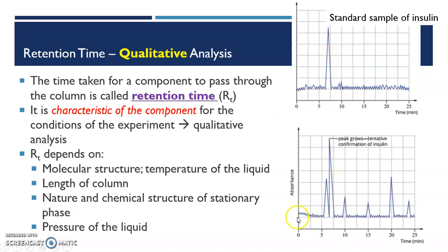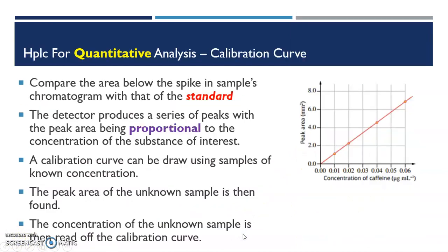And then we run the sample through the same machine and the same condition, and we are basically looking for peaks with the same retention time. If that's the retention time for insulin, and you have the same peak at the same time, that means that this sample does contain insulin. So that is for qualitative analysis. And you notice that retention time does depend on molecular structure, temperature of liquid, length of column, stationary phase, and pressure of the liquid as well. So we need to make sure that this standard chromatogram is produced in the same condition as the chromatogram of the sample that we want to test, confirming insulin there.